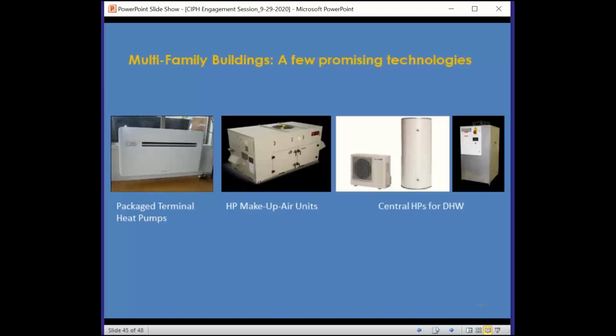The final technology to highlight is heat pumps, central heat pumps to provide domestic hot water in multifamily buildings. There are a couple of different options available in the market. You can use a CO2 heat pump that's available from Sanden, the only one in North America right now that's widely available. It's popular because you're able to chain together a bunch of these units, and because of their small size, you'd be more flexible in where you place them in a building.